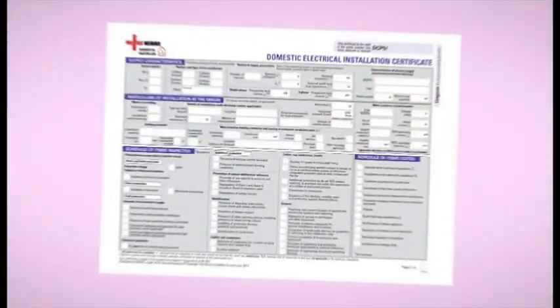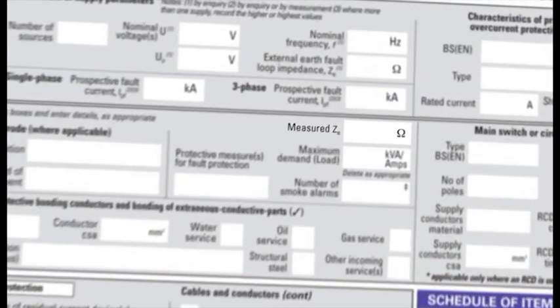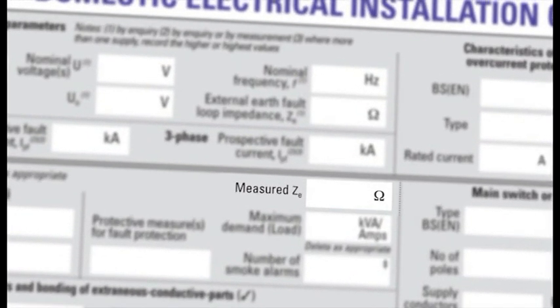The final box included with supply parameters is external earth fault loop impedance, ZE. Now on the domestic electrical installation certificate, this is not a measured value, but a declared value determined by inquiry to the electricity distributor or taken from the design information. The declared value of ZE for a TNCS supply is 0.35 ohms, and for a TNS supply is 0.8 ohms. However, on the electrical installation condition report, it requires just a measured value. Now, if we look back at the domestic electrical installation certificate, we can see that there is another box for a measured value of ZE as well.